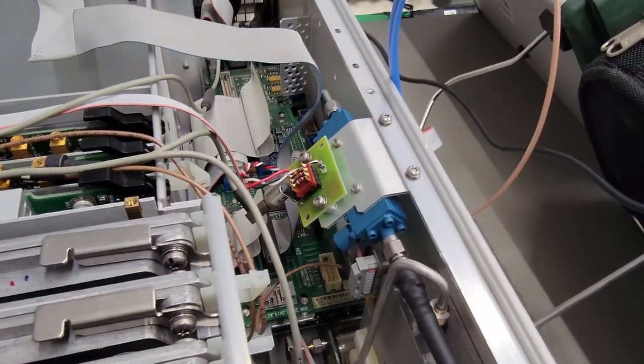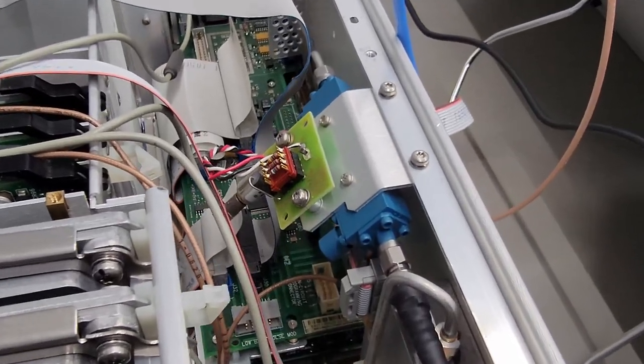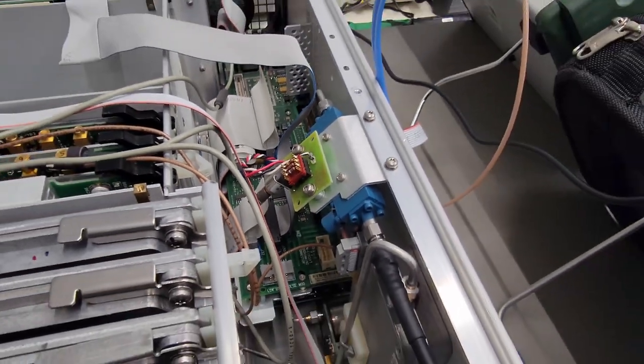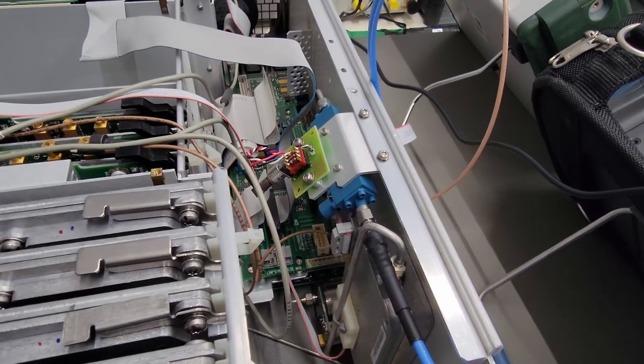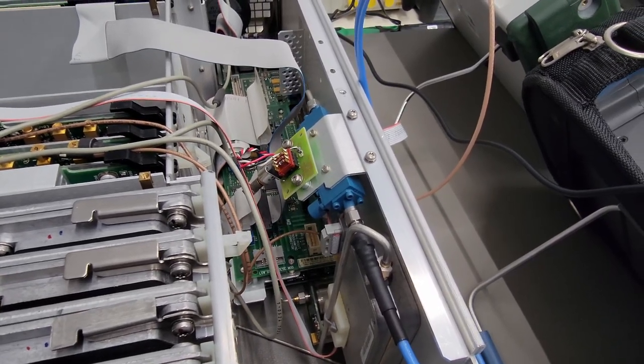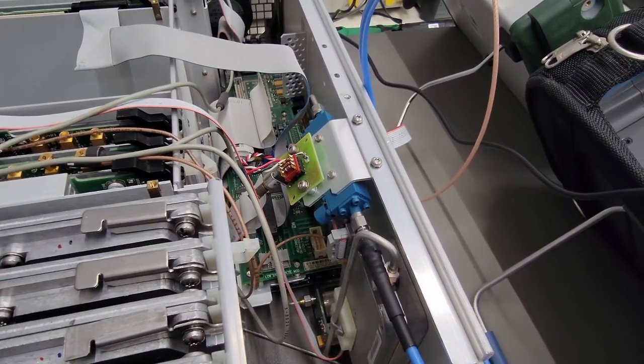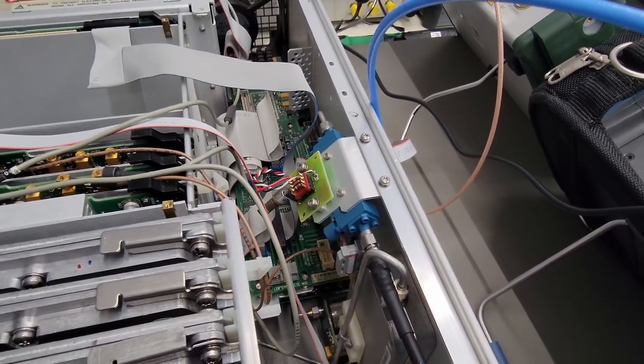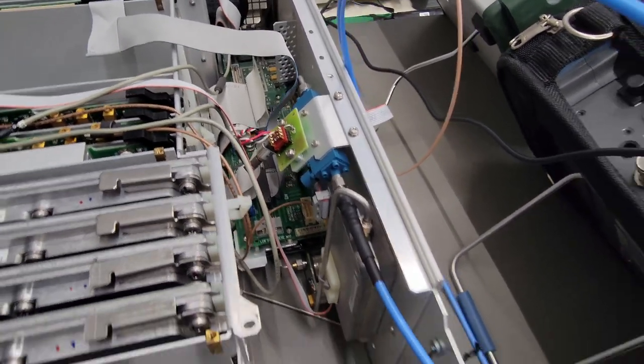this detector and directional coupler combination here. So that could be one thing that's causing the ALC not to regulate correctly and for the amplitude to be low. And we'll just work our way back from the RF path there.